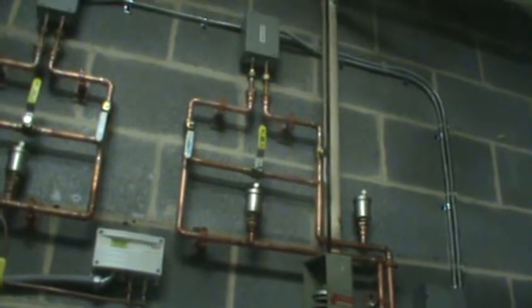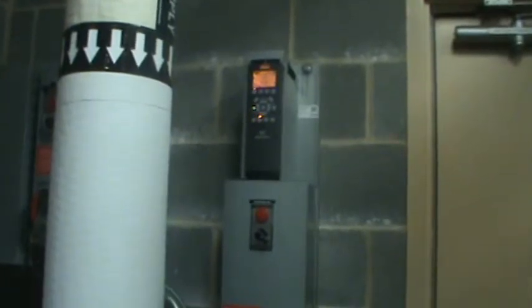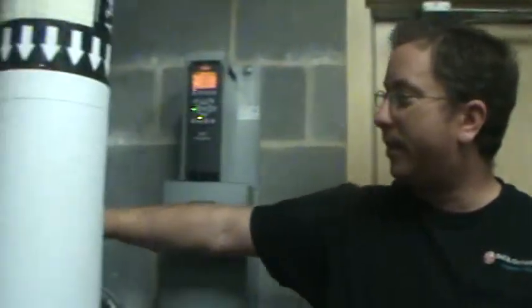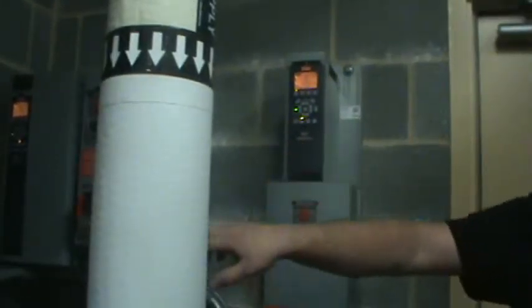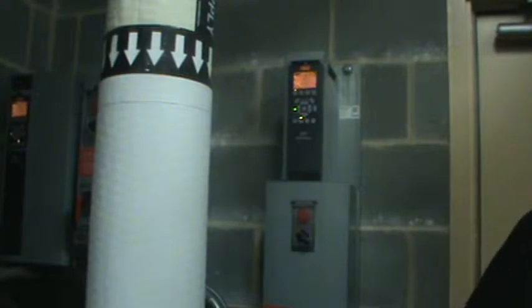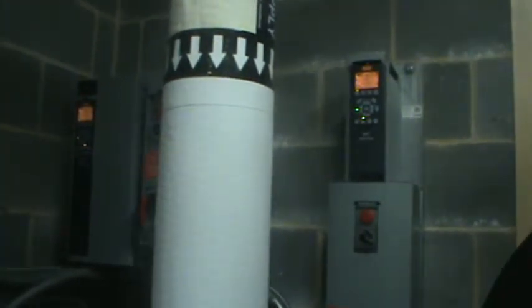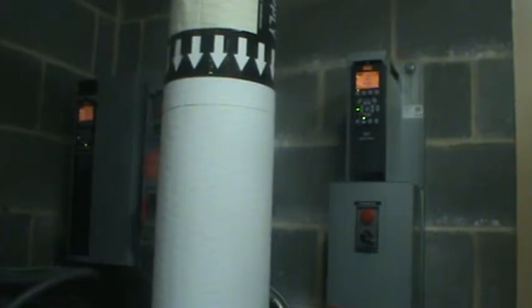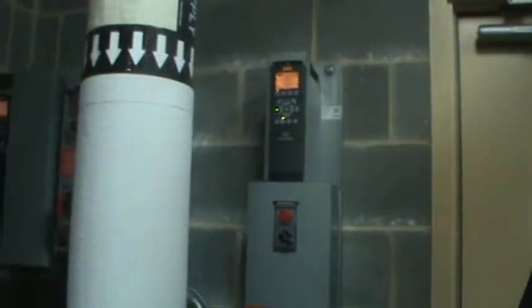And all the systems, other than physical location in your other buildings, it's all pretty much the same. You're going to rotate them back and forth. It's all manual. You don't have an automation system. Like right now this one's running. It's in auto. Hit auto on this one. Hit off on that one. A week or so later, whatever your rotation plan is, do the opposite. One will ramp up, one will ramp down. You never really have a lack of flow in the building. You will have an odd pressure differential for a short period of time. Nobody will ever see it. Okay.